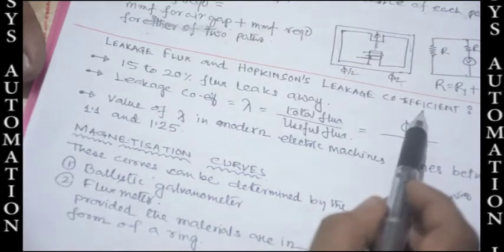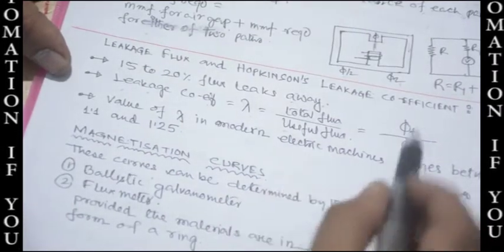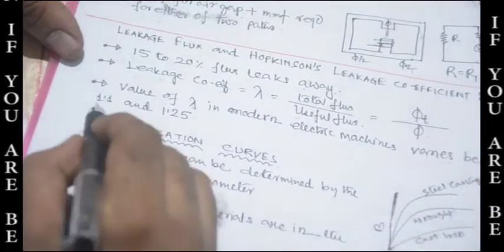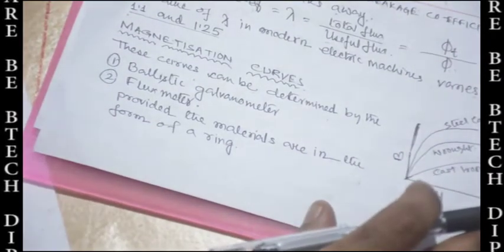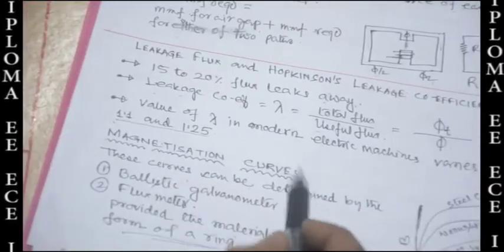Leakage flux is also described by Hopkinson's leakage coefficient. About 15 to 20 percent of flux leaks away. The leakage coefficient lambda = total flux / useful flux = φ_t / φ. The value of lambda in modern electrical machines varies between 1.1 to 1.25. Magnetization curves can be determined using a ballistic galvanometer or flux meter, provided the materials are in the form of a ring.